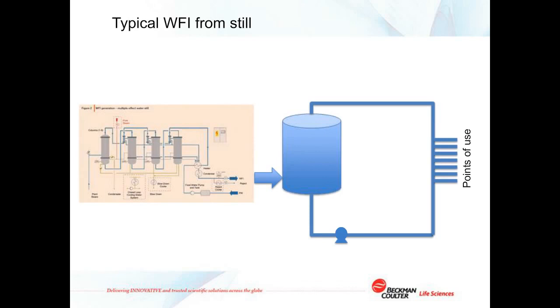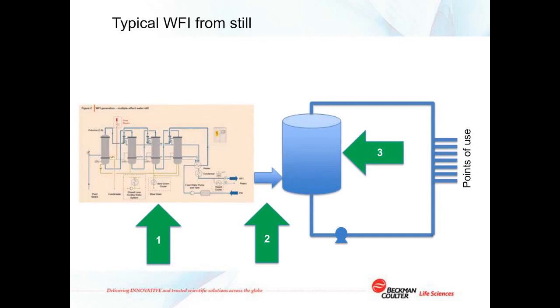Producing water for injection using a still is a very energy-consuming process. The still itself uses vast amounts of energy to heat the purified water until it turns into steam. The steam is then condensed to form water for injection. As the water for injection is made hot, it's transferred into the storage vessel and distribution system hot as well. To discourage microbial buildup in the storage tank and the distribution loop, they're both kept hot. Although the storage vessels vary in size, commonly in a large manufacturing facility, they contain thousands of liters of water, and this must be heated and maintained at temperatures higher than 65 degrees centigrade to prevent microbial excursions.